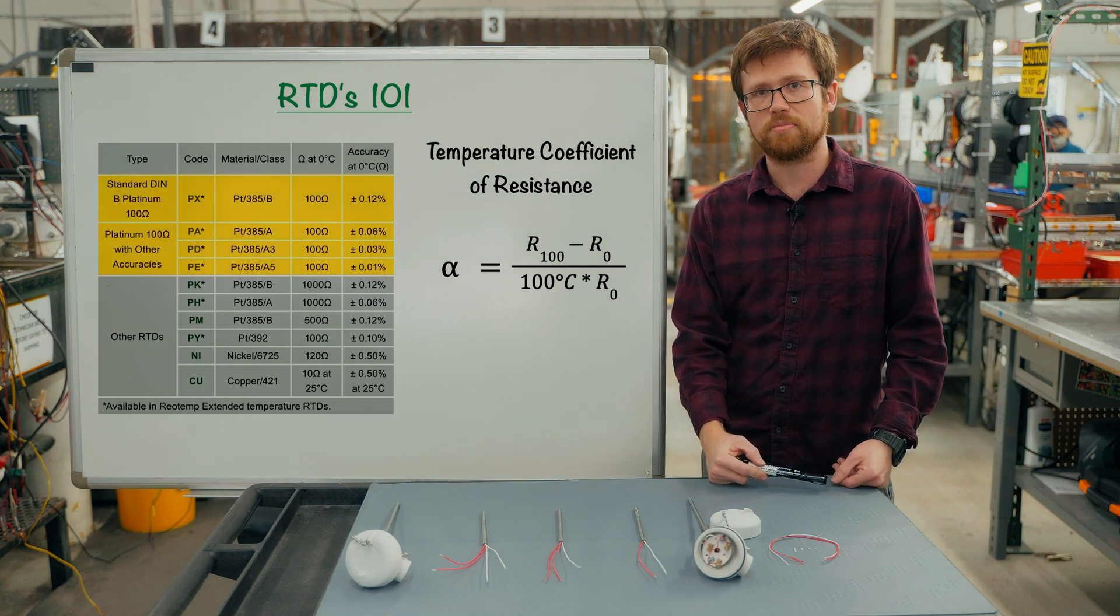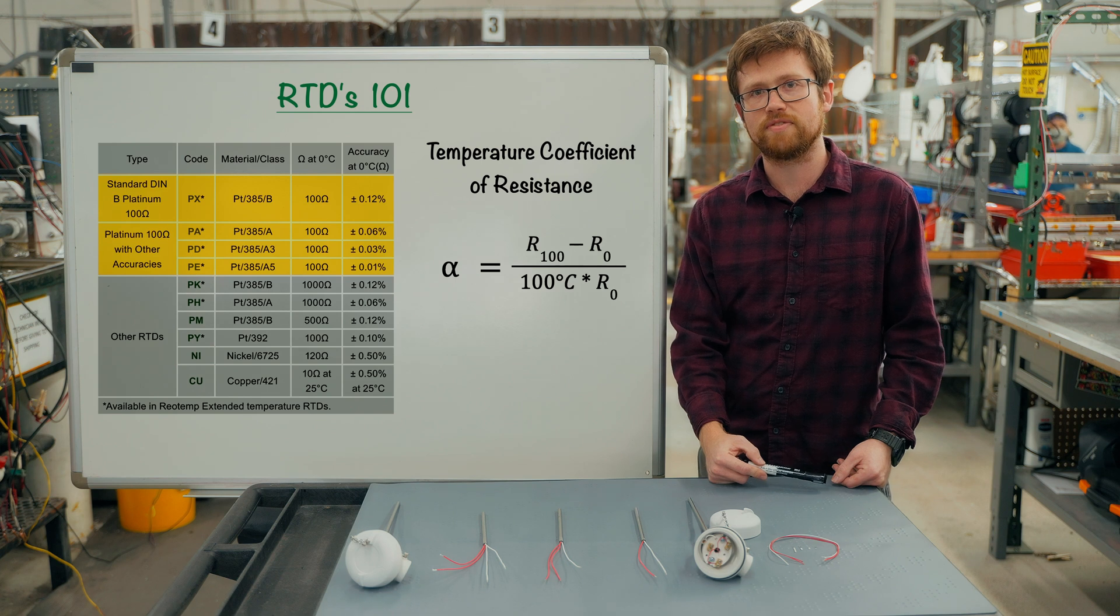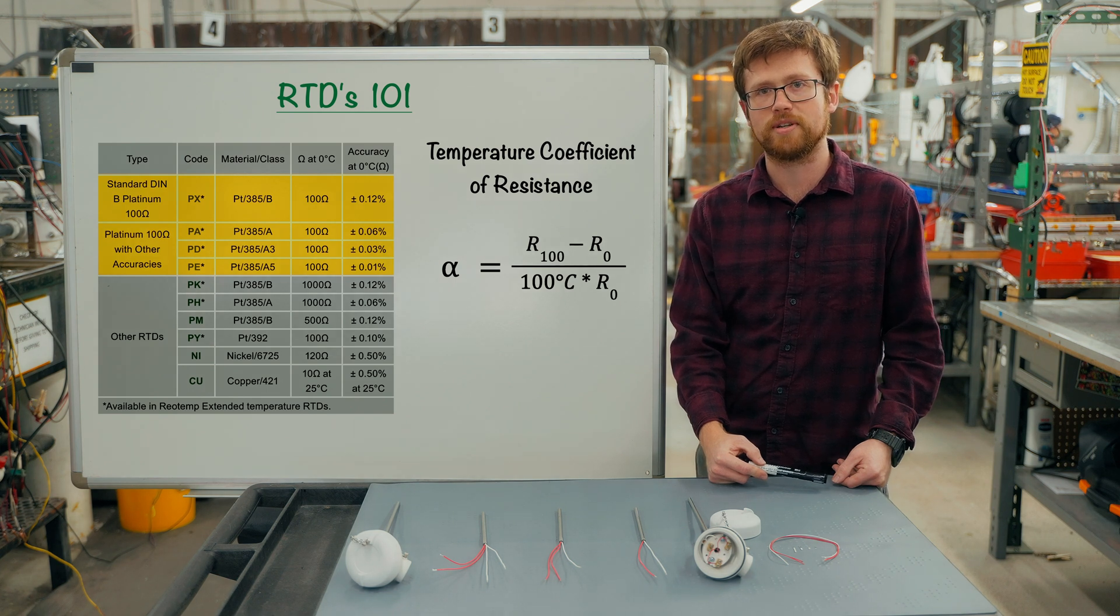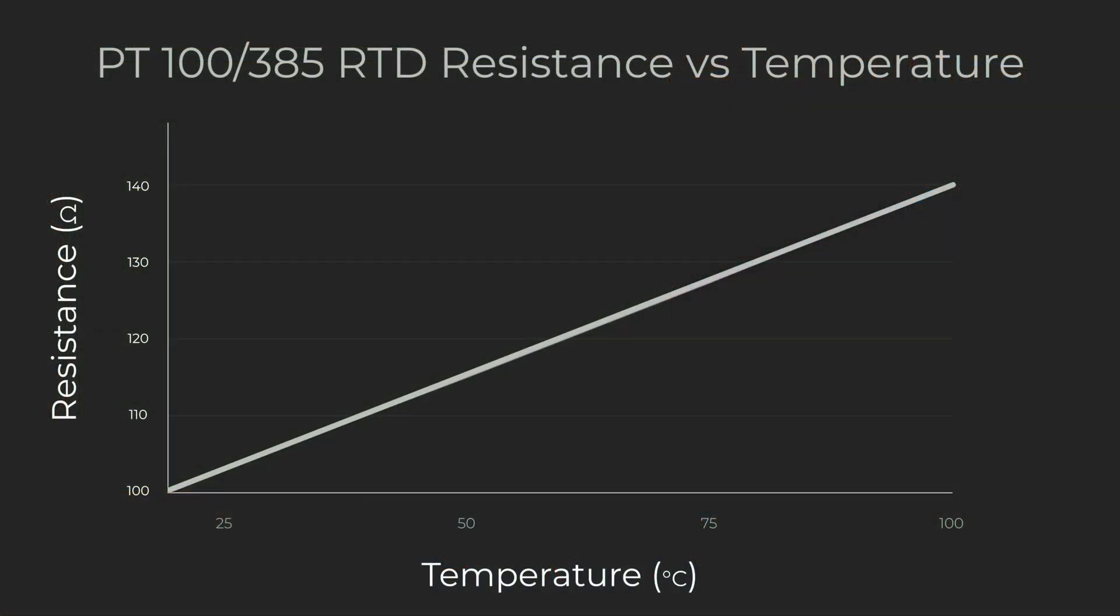In the industrial world, PT100/385 alpha RTDs are by far the most common. This terminology means that the RTD has a resistance of 100 ohms at zero degrees C and a slope of resistance from zero to 100 degrees C of 0.00385 ohms per ohms degree C.